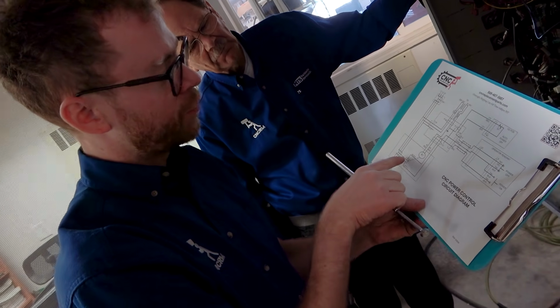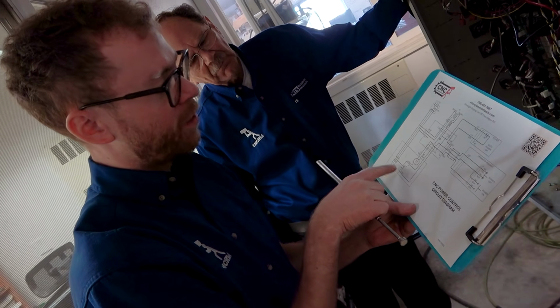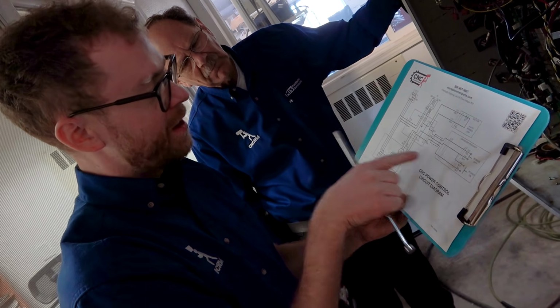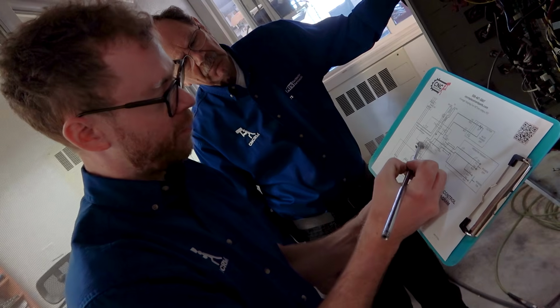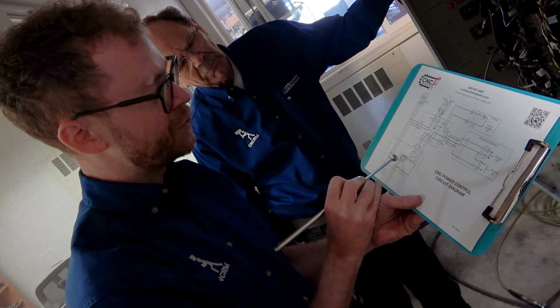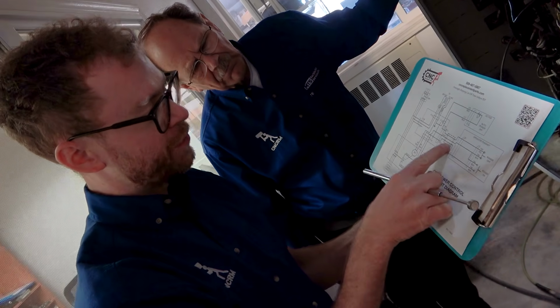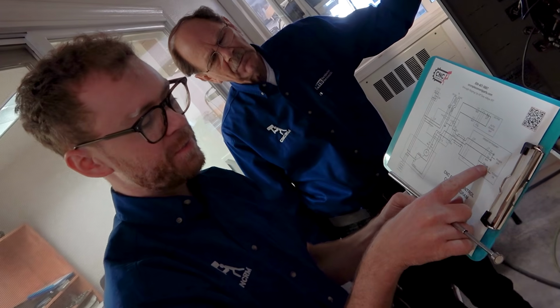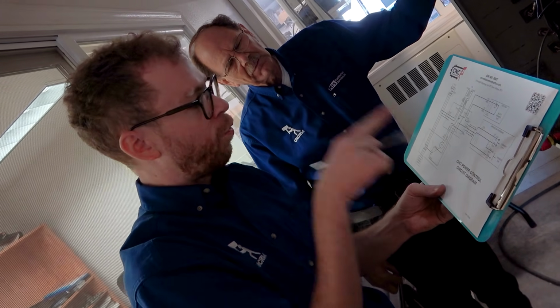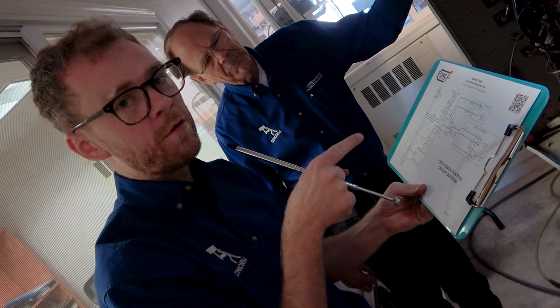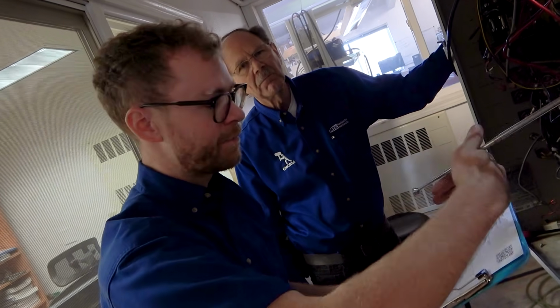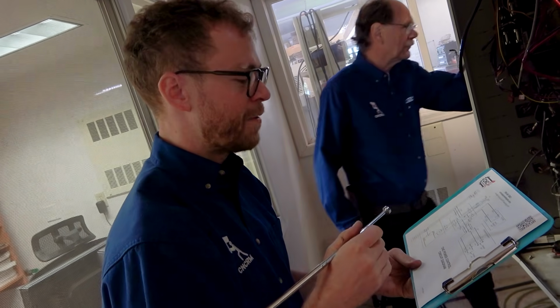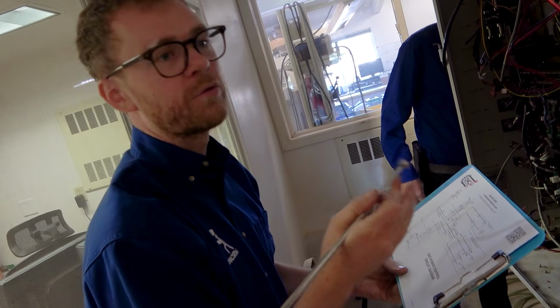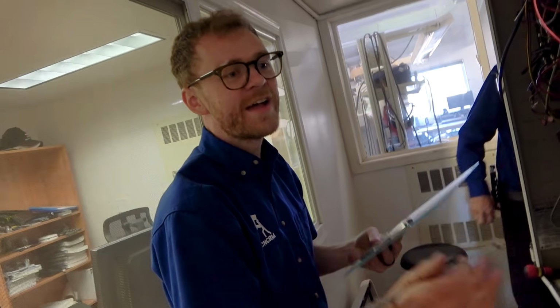Then I can say, is there voltage on the top of this contactor? We're going to work our way all the way down, because there should be voltage through the coil, and there should be voltage here. And then there should be voltage all the way down to here, but there shouldn't be any voltage there. So I work my way down, and where I expect to see voltage and I don't is where the problem is. Sometimes you can cut the problem in half and say, is the problem here or is the problem there?